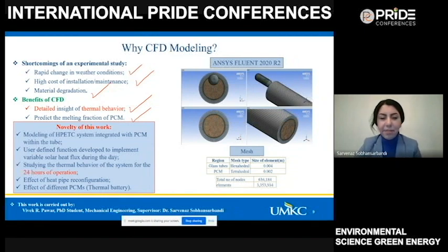Because we had a couple of issues previously: we left the system outside during summertime, and we did not know what was going on inside the collector, and then it was overheated, the system was not cooled down, so it started overheating, the material started degrading, and then we had a leak from the collector. So that's not what we need to have in any experimental work.